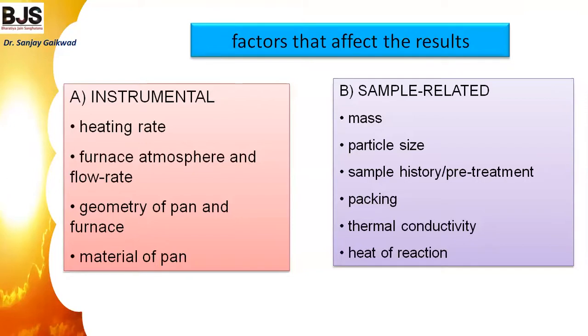Factors affecting TGA include instrumental factors: heating rate, furnace atmosphere and flow rate — whether dynamic air, static air, or nitrogen is used — and the geometry of the pan and furnace. The material of the pan also affects the analysis. Sample-related factors include mass, particle size, sample history, pre-treatment, packing, thermal conductivity, and heat of reaction.